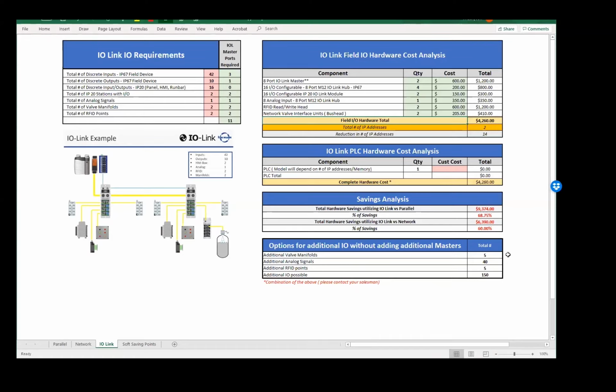But on the contrary of that, it also gives you ultimate flexibility, because if a customer comes to you and says, I want to add 160 IO points to this machine, 5 more RFID processors, 10 more analog signals, you can now say, okay, I'm going to have to buy some hardware in the field.